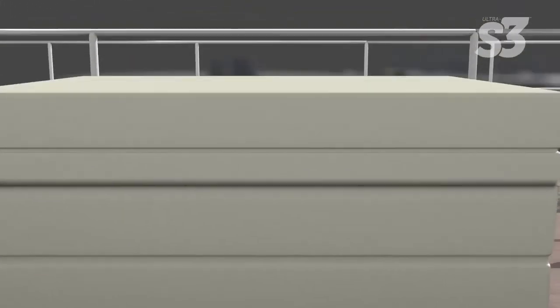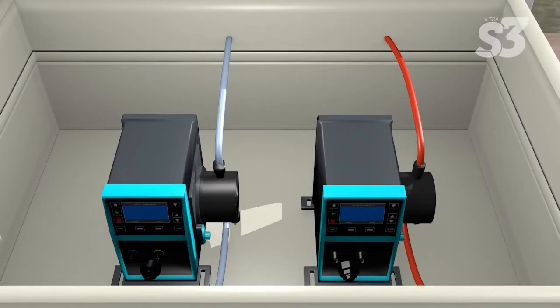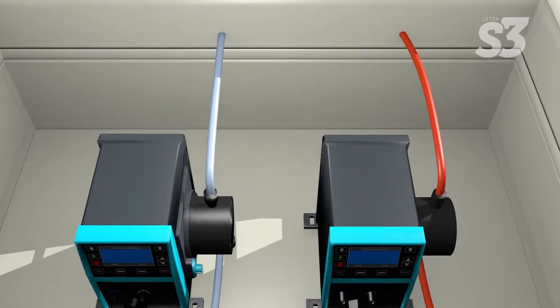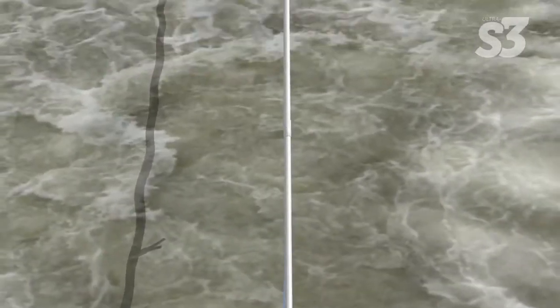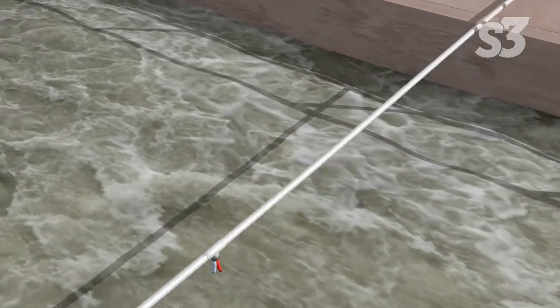Using peristaltic metering pumps, introduce the Ultra S3 and oxidant into the system. In this example, we're using hydrogen peroxide for the oxidant. Deploy the solution into the system as far upstream as possible to provide maximum treatment time.